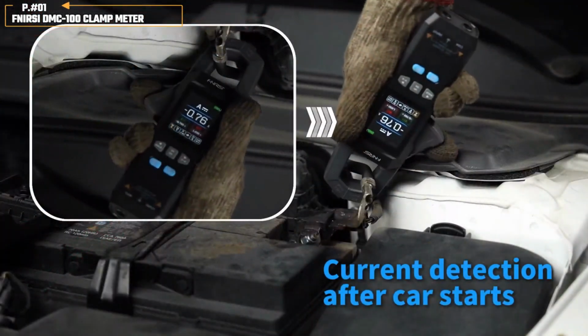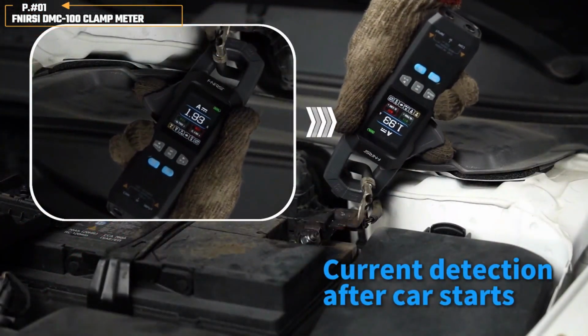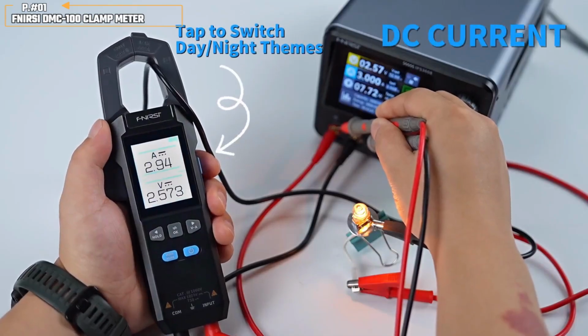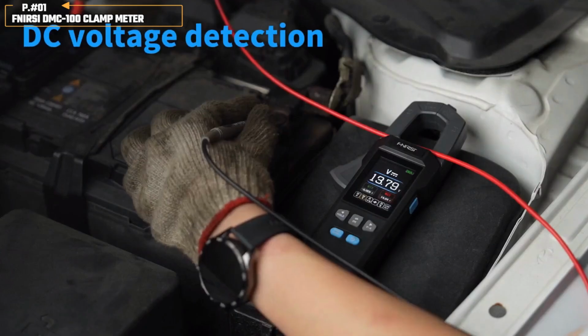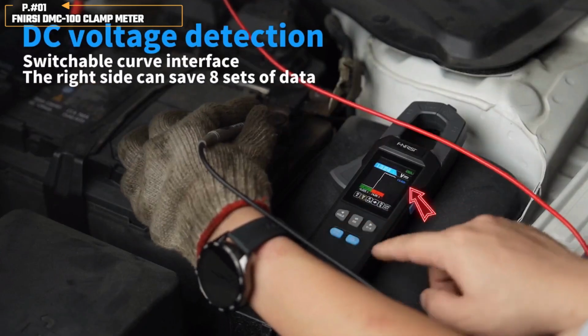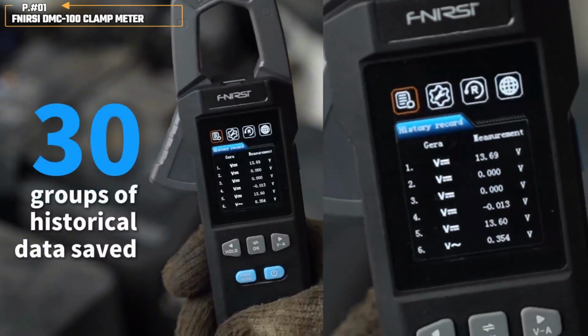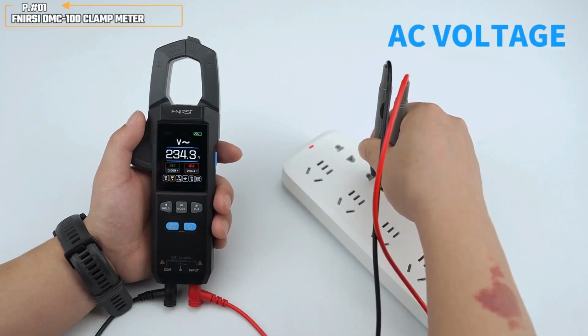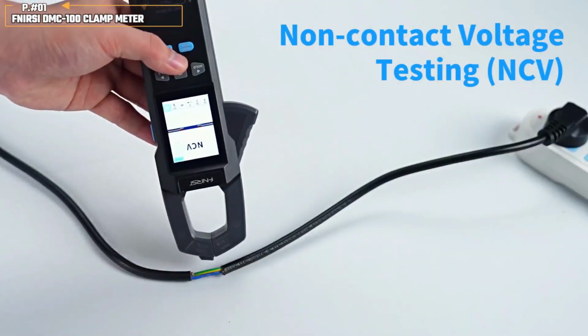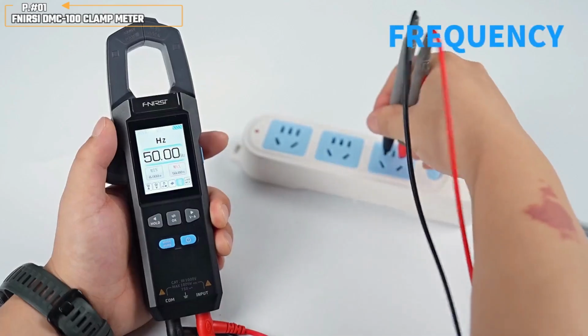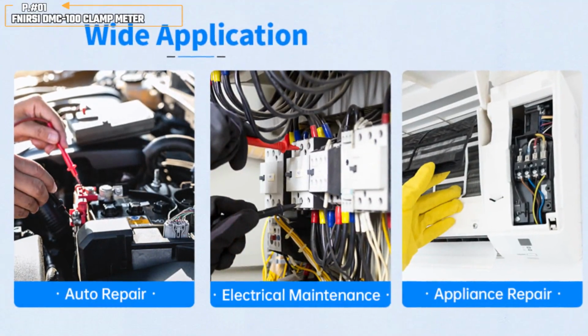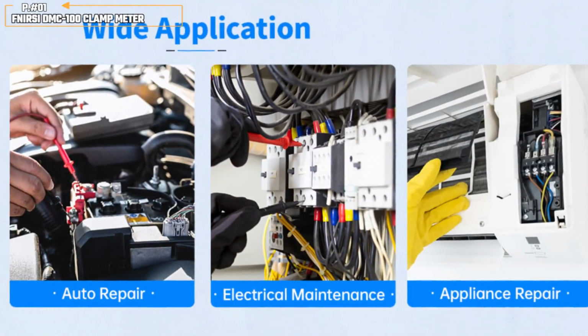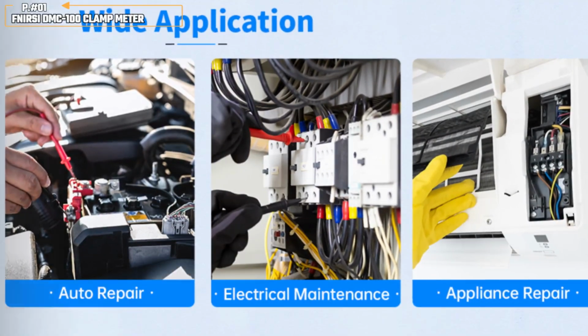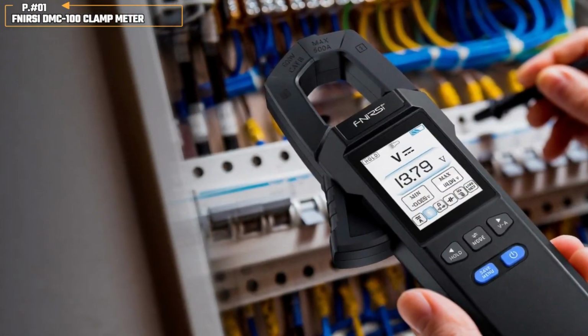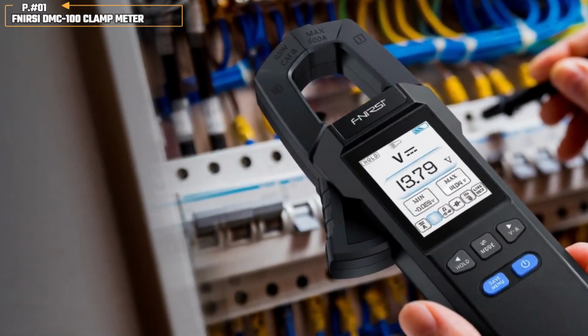The 10,000 count True RMS system measures AC and DC current up to 600 amps. It also handles AC voltage up to 750 volts and DC voltage up to approximately 1,000 volts. Power mode can display clamp current and test lead voltage together. The meter also covers resistance, capacitance, frequency, temperature, continuity, and diodes, along with NCV and live wire detection. The built-in 1,500 mAh battery charges through USB-C, while the meter can store up to 30 groups of readings. Its compact 25mm jaw works well for automotive, solar, and general electrical testing.